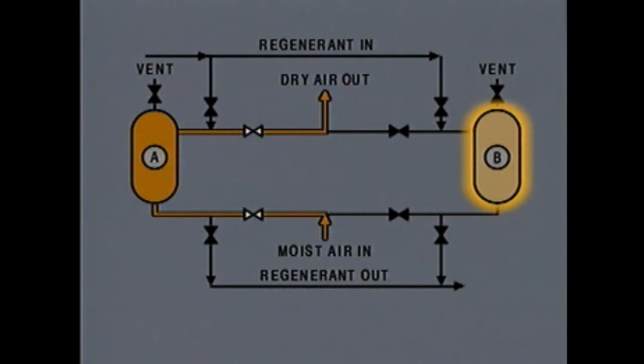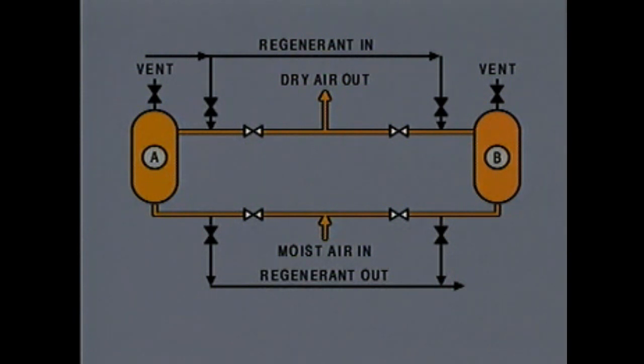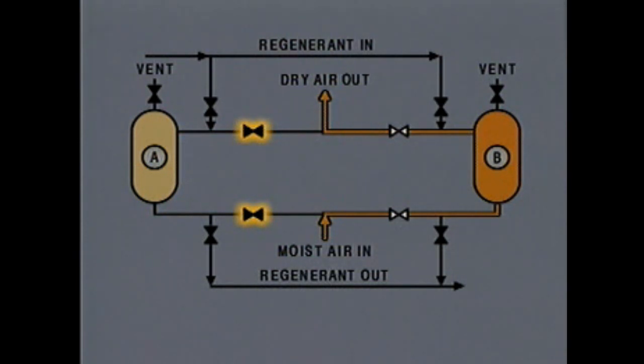To put dryer B in service so that dryer A can be isolated and its drying agent regenerated, these valves are opened. This allows air to pass through the drying agent in dryer B and out of the system. Closing these valves isolates dryer A.